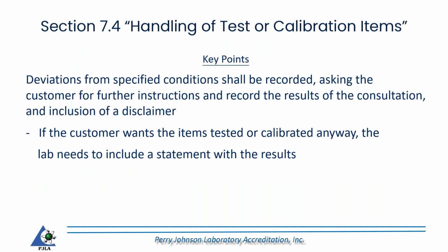Just a couple of key points before we move on that we want to capture from that long clause. Basically, the deviation from specified conditions, whatever they happen to be, shall be recorded, or in other words, a record needs to be made, asking the customer for further instructions. So you're asking the customer, hey, you're outside these specific instructions. What do you want us to do? Then the record of the results of this consultation and inclusion of a disclaimer. If for whatever reason the customer wants the items tested or calibrated anyway, the lab needs to include a statement with the report. In other words, the test or calibration report being produced shall include the deviation within the report.